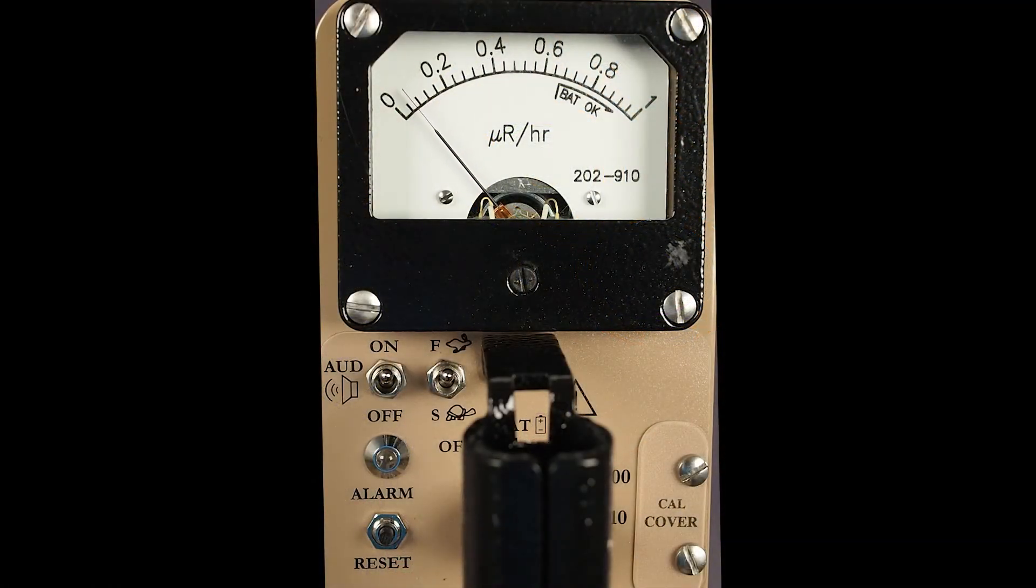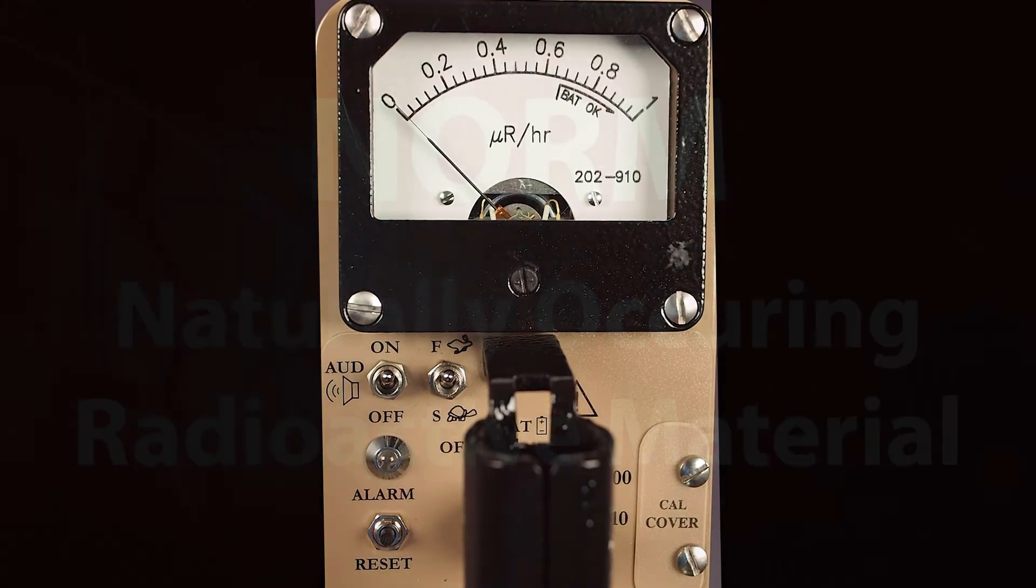The meter can sense a detector failure if it receives no counts from the detector for 8 seconds. In the event this occurs, the instrument will beep rapidly and displays a meter reading of zero. The instrument should be taken out of service until it is repaired.